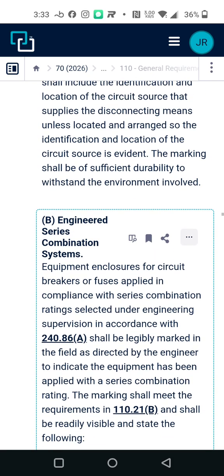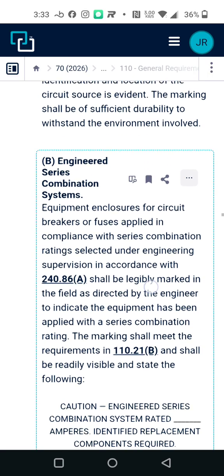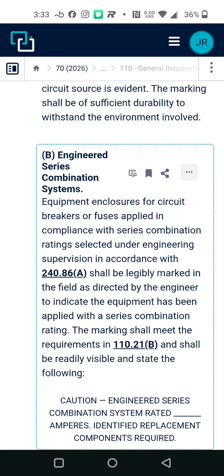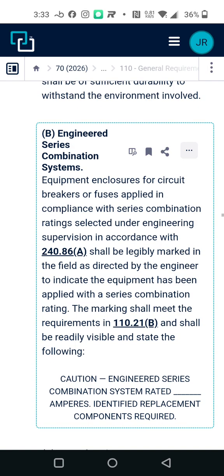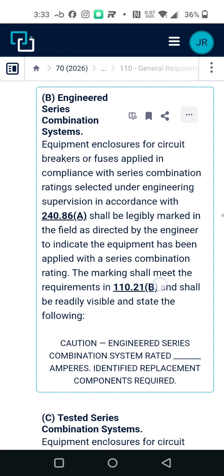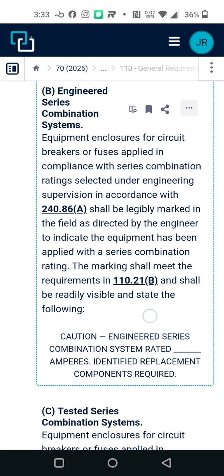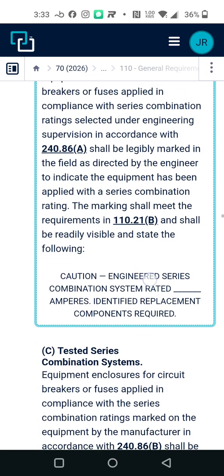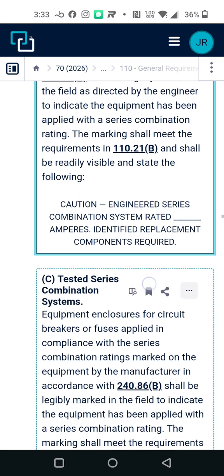Engineered series combination systems. Equipment enclosures for circuit breakers or fuses applied in compliance with series combination ratings selected under engineering supervision in accordance with 240.86(A) should be legibly marked in the field as directed by the engineer to indicate the equipment has been applied with the series combination rating. The marker shall meet the requirements in 110.21(B) and should be readily visible and state the following. Caution, engineered series. Okay, so some of these things I'll go through, some of the things I'll just scroll through, okay?